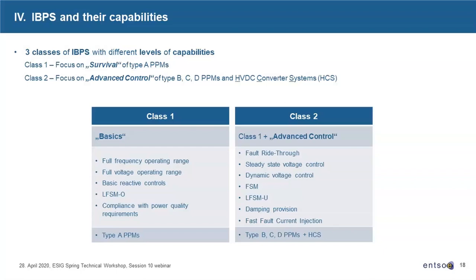Advanced capabilities are required of all other generators in the system. Typically, as we introduced in the network codes requirements for generators, there are four types called A, B, C, and D. As I say, type A shall be able to do the basics, and the advanced control capabilities and system supportive behavior are to be expected of all the others: type B, C, and D power park modules, and also HVDC converter stations. They are capable of these features, which you can read here, like fault ride-through capabilities, voltage control, both at steady state and dynamic level, advanced frequency control, damping provisions, and fast fault current injection for stability after incidents to the system.